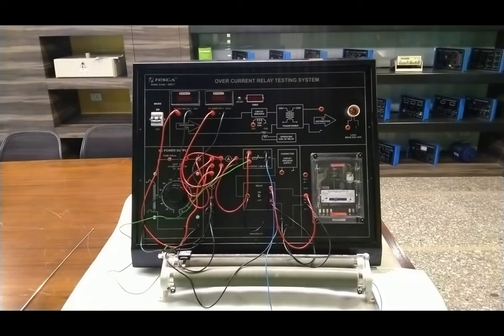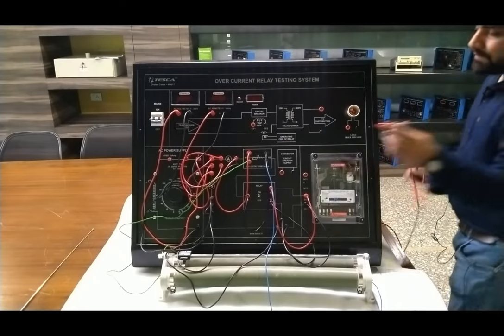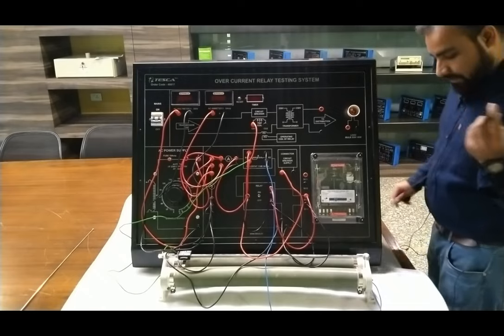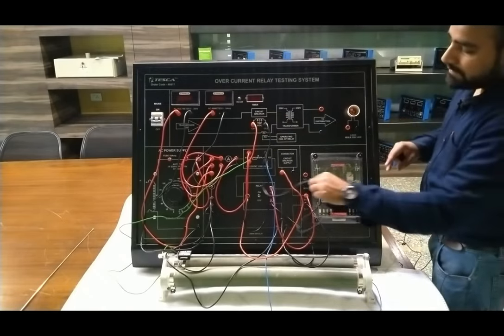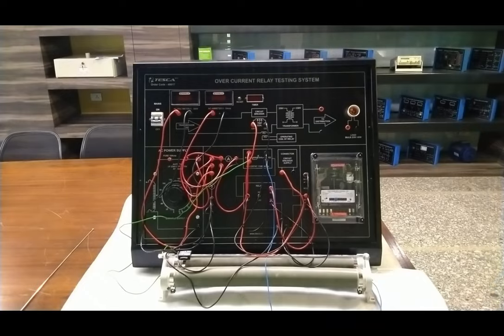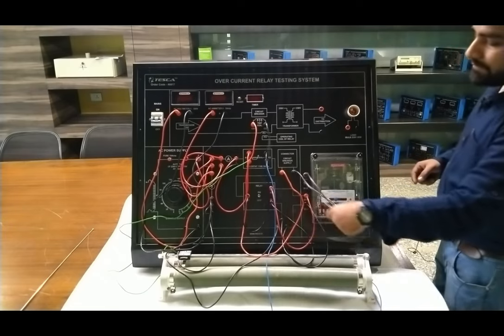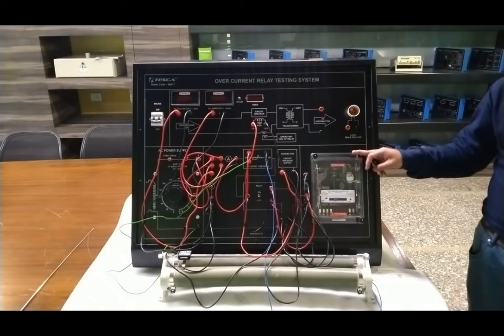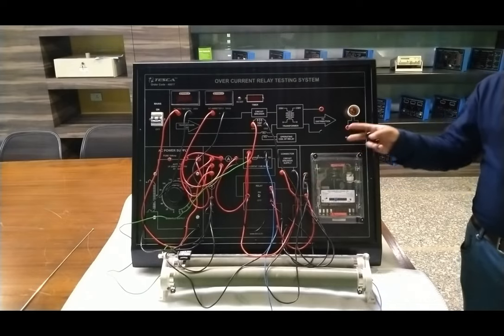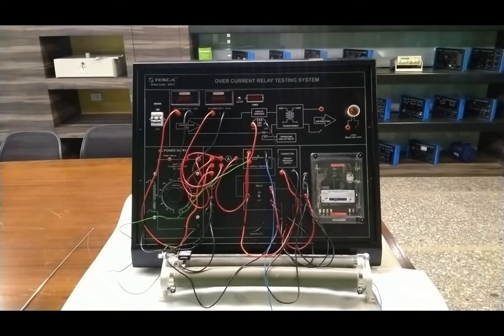Now for the circuit breaker connections, the contact of the circuit breaker will be connected. We will connect the red one with CB1, and the black one will be passing through the relay terminal, so that the circuit breaker direct connection will be passing through the relay. Whenever the relay is energized and tripping occurs, the NO contact of the relay will change to NC, and the circuit breaker coil will be tripped, opening the circuit breaker to the load. Now we will connect the load.